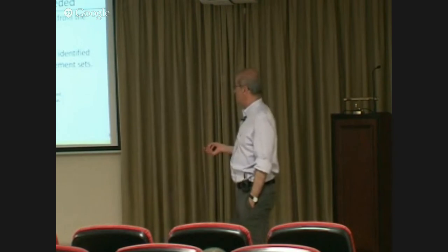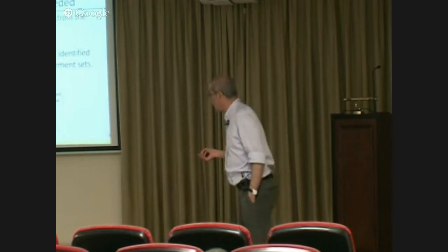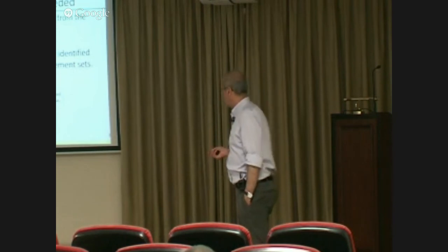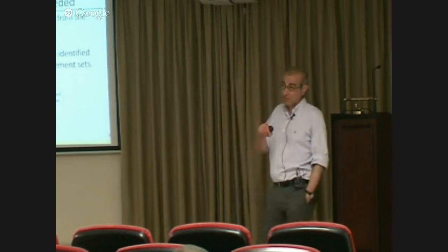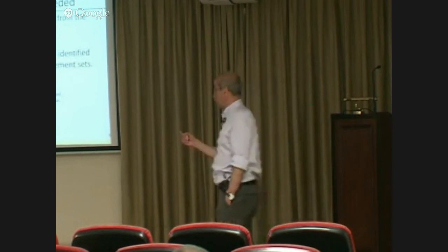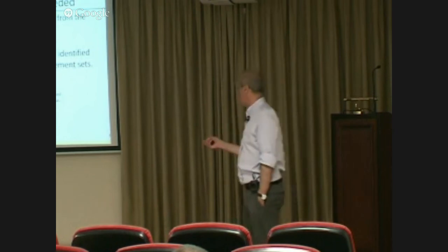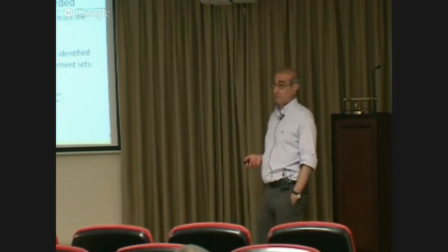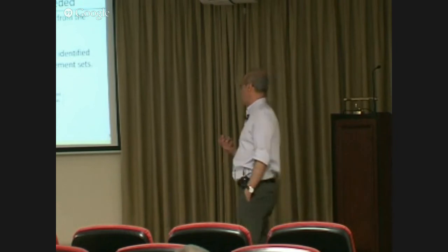The nice thing is, if you use them as measurements and go through the state estimation bad data logic, that logic can not only identify and throw out SCADA errors, but also PMU measurement errors. So if you have a bad PMU, it will be thrown out by the bad data processing function, whether you're using weighted least squares or LAV, it doesn't matter.